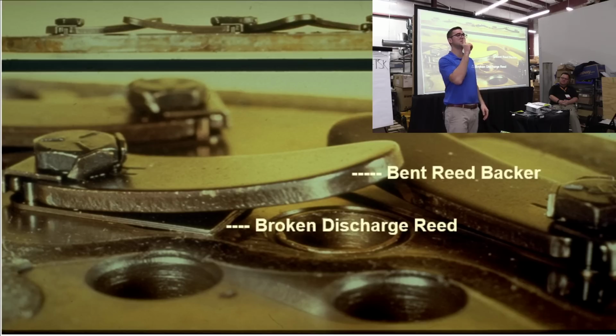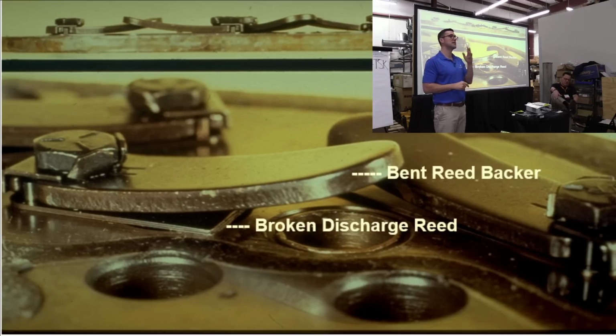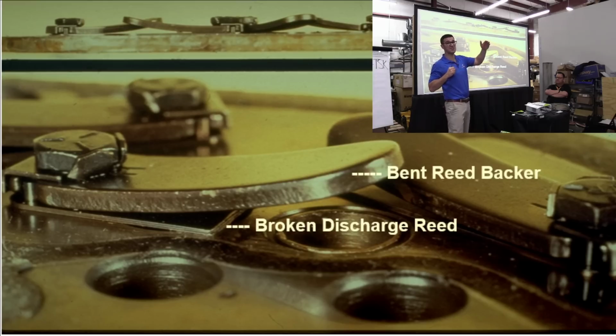So now what's happened? Let's say on one cylinder, it's a 3D compressor, so it has 3 cylinders and 1 busts. Is the compressor still going to run? It's still running. But what's happening now? What's going on right here? What's pushing on that piston now? Discharge pressure. So that one piston is fighting the discharge pressure of the other 2. Everybody following me right now? Okay.